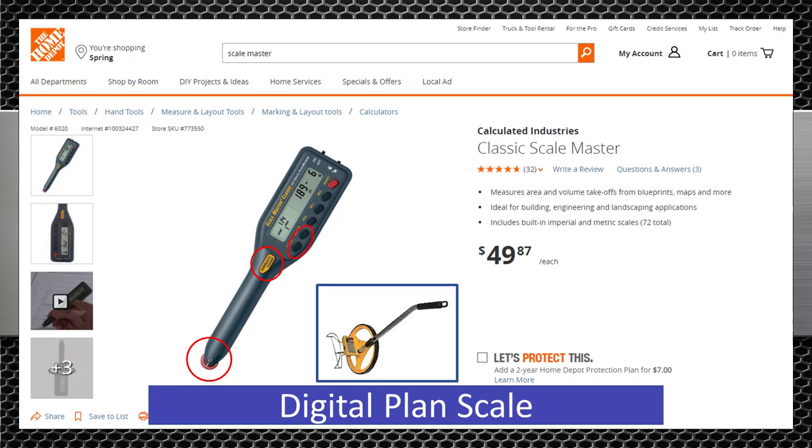These buttons allow you to set the scale. It has preset scales for engineering like 10 feet per inch and up and architectural scales like 16th, 8th and quarter inch per foot. You can also set custom scales which comes in handy if you know the distance between two given points but do not know the scale of the drawing. A lot of times when you do not know the scale you can measure what you know to be a three foot doorway, set the distance and the scale will be set for the entire sheet. You can also use other buttons to measure square footage and volume. You can estimate with an architectural scale but this is much faster.